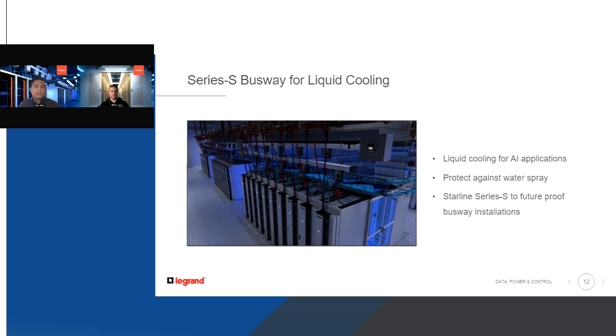The other busway related item that we're seeing AI influence is this shift to liquid cooling, or a hybrid between liquid and air. We're getting a lot of questions around preventing damage from water because of the liquid cooling. So we do have an S-Series busway that offers IP54 protection. We're starting our first few deployments of it next year, and this will help future-proof busway installations if liquid cooling is a concern for your data center.